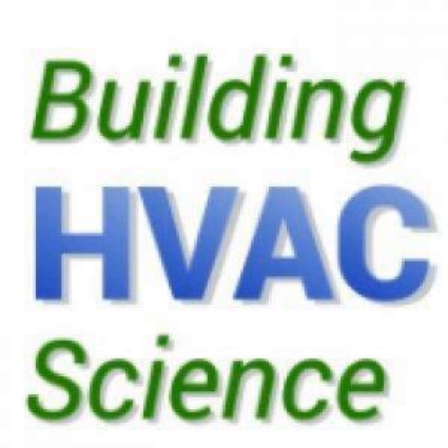For Aeroseal, a question I get a lot is if you have a system which is already way oversized, someone didn't do the Manual J, they've replaced it two or three times, and every time they went up a half ton, and it's got a high static pressure, I wouldn't seal it because it's relying on the leaks in that system to not hurt the blower. HVAC equipment's generally designed for a half inch of water column. What I say and what we train is if it's at 0.7 inches of water column or higher, don't seal it. That's a candidate for talking more about adding additional ductwork or doing something else to remediate the problem rather than sealing up already undersized ductwork. Yeah, it needs to be leaky because of poor design. Exactly. And unfortunately, a lot of guys do that. They get a homeowner that just wants the best of the best and the biggest of the biggest. Well, you can do that, but it's not good for anyone.